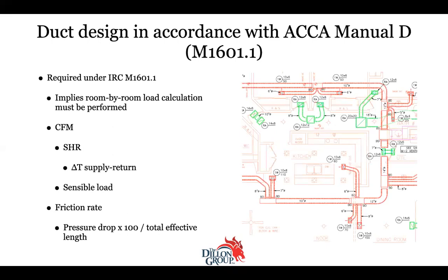So duct design in accordance with ACCA Manual D, again, it's required. It implies that a room-by-room load calculation has to be done, because you can't do a Manual D on a block load. And you look at the cubic feet per minute, what's the airflow? And then you look at the sensible heat ratio, which is how much of the heat is sensible versus latent. And then you look at the delta T, the temperature drop across the coil between supply and return, and the sensible load.